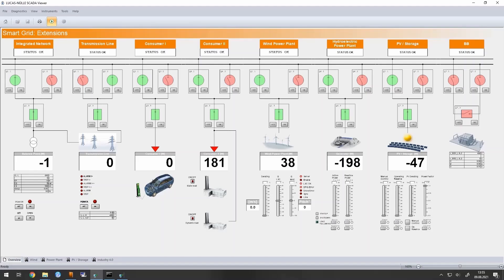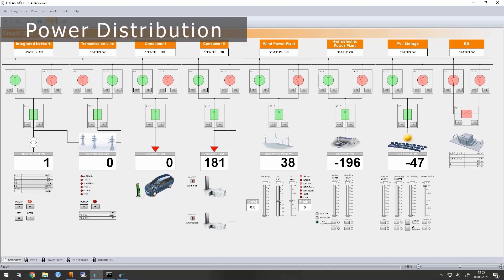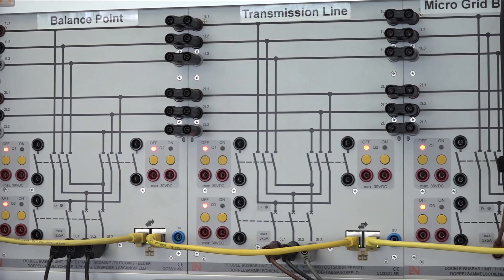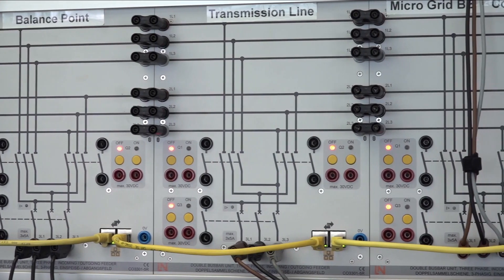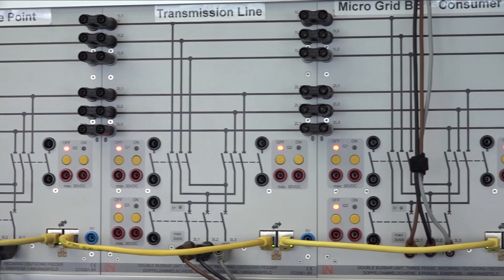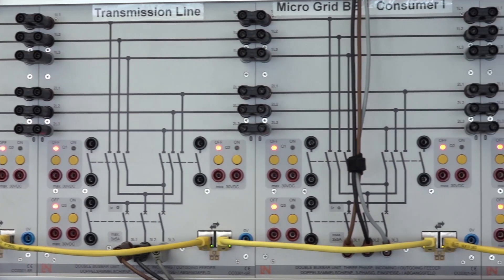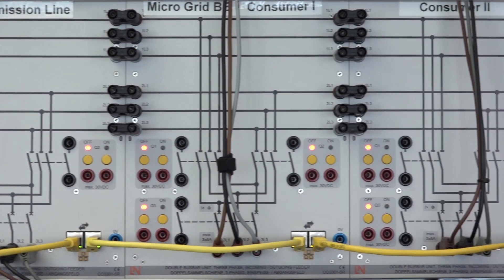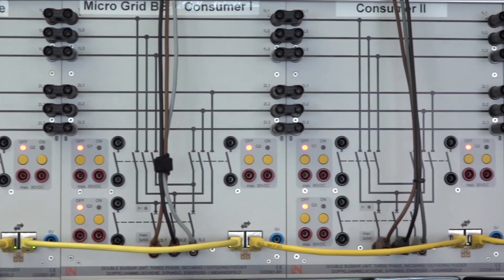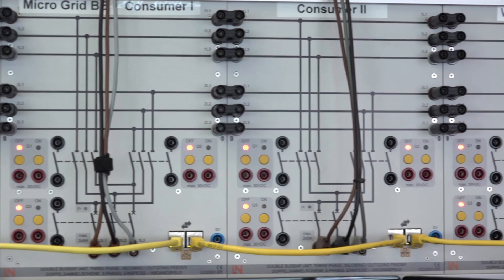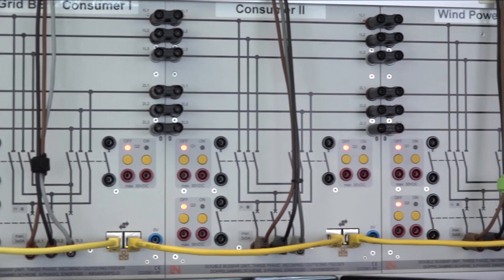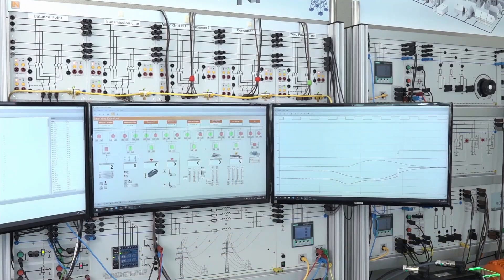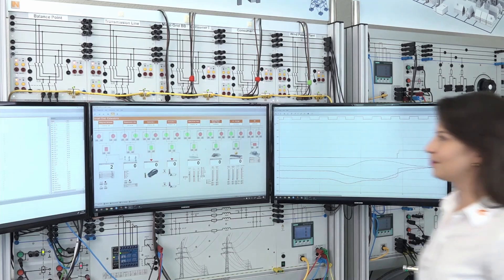Power generation and consumption can be coordinated by means of a smart grid. Power distribution includes networking and electrical interconnection of sources or sinks. This is realized here using the double bus bar system. Each panel consists of two isolators and a circuit breaker and can be operated manually or by means of SCADA interface.